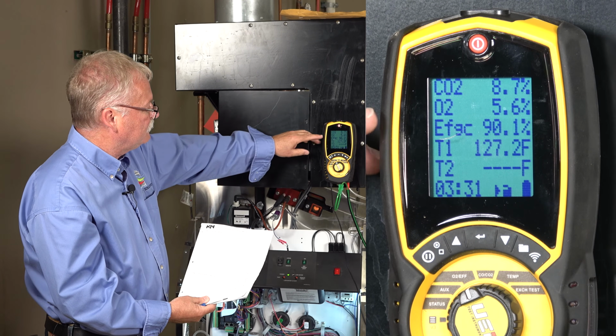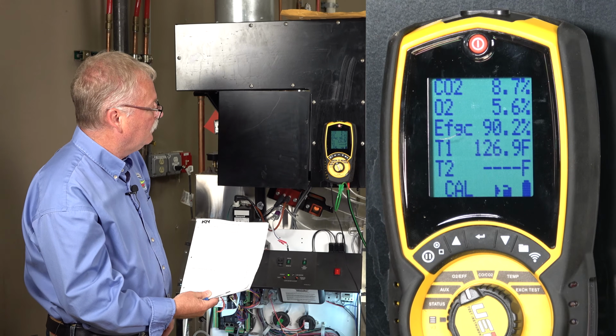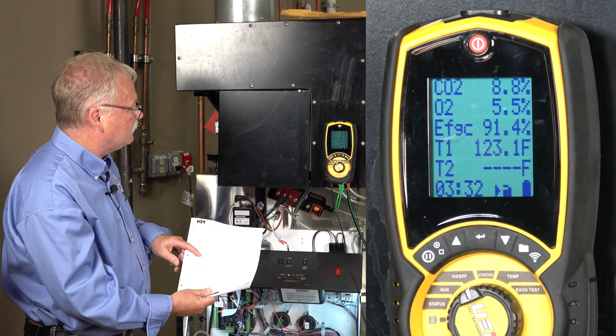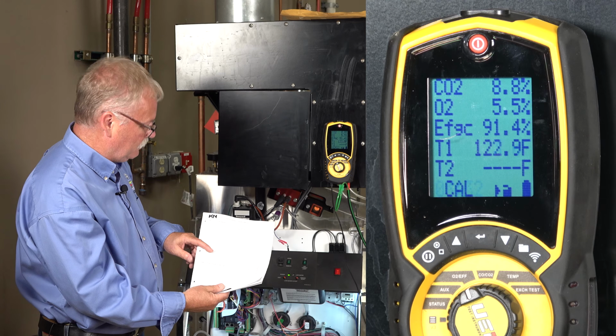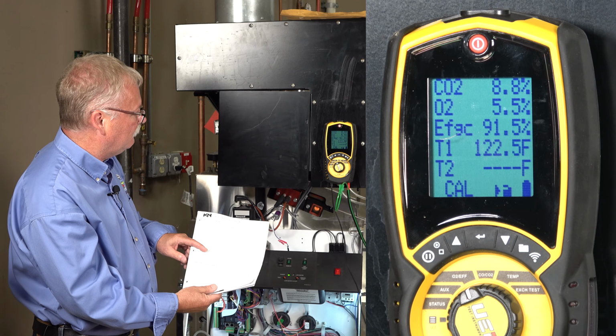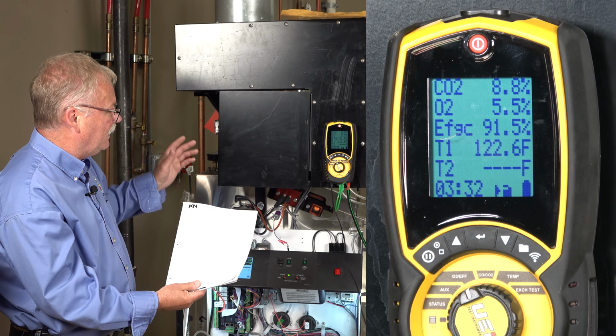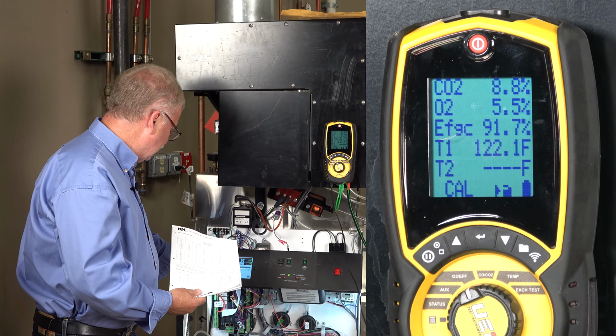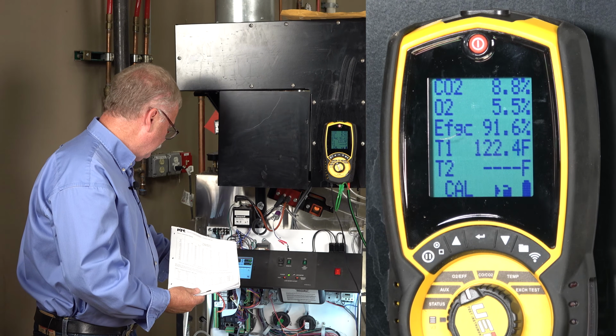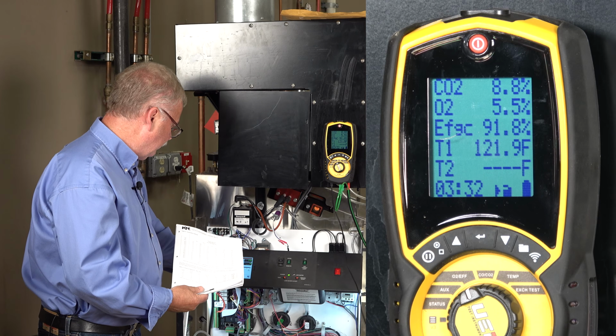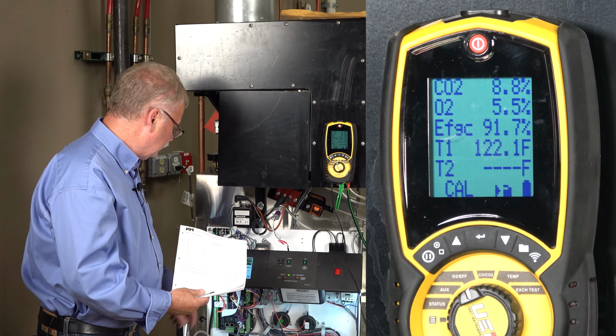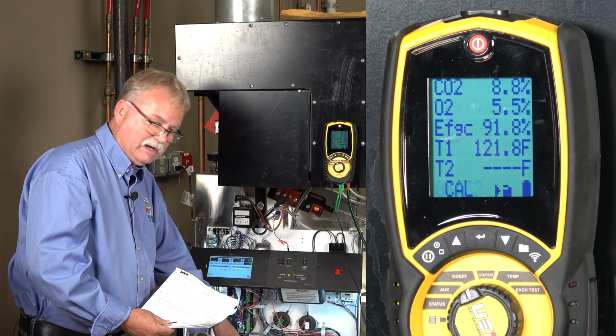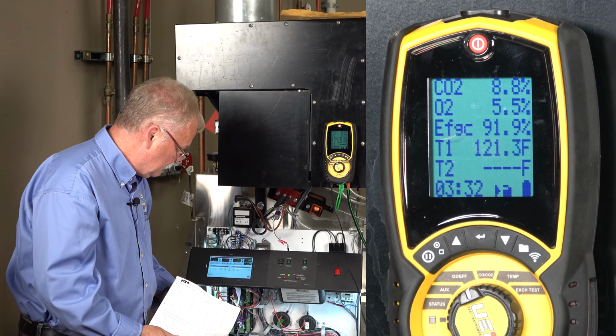As you can see, our efficiency is 90.1. So let's take that as 8.8, which is a good number. 91.4, a good number on efficiency. 91.5. And let's lock that in. And let's go to our high. Let's see what it does. Now I didn't take that out because I'm not going to adjust that anymore on the low side.